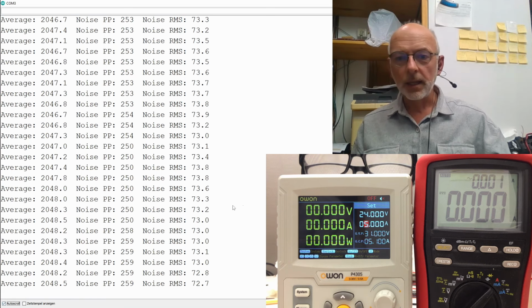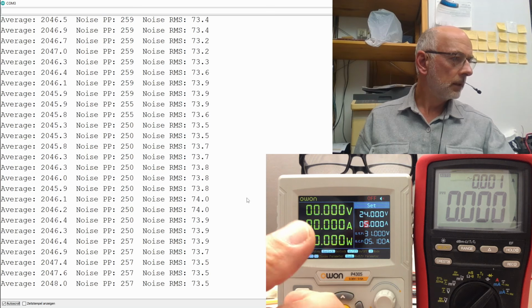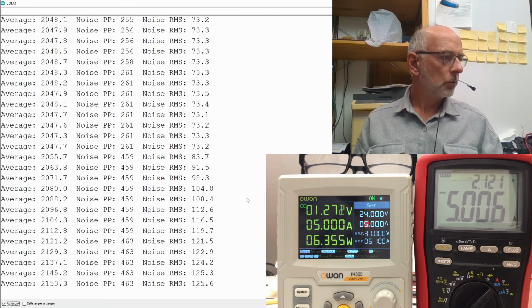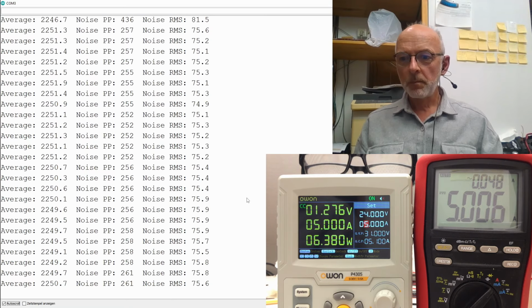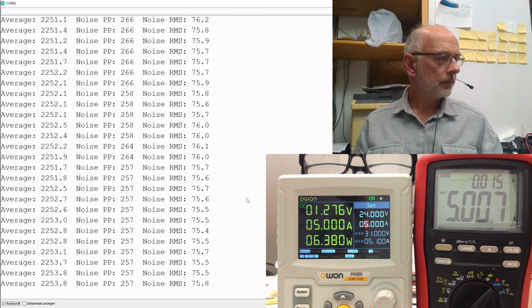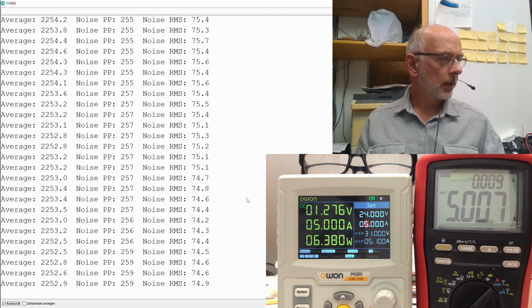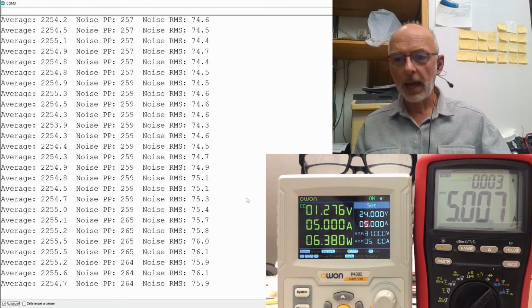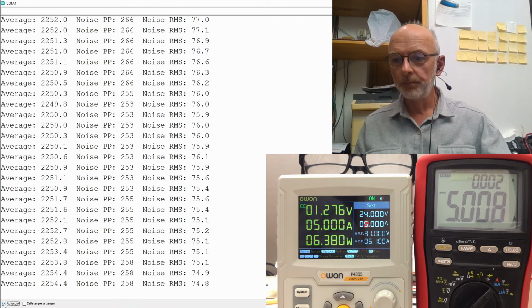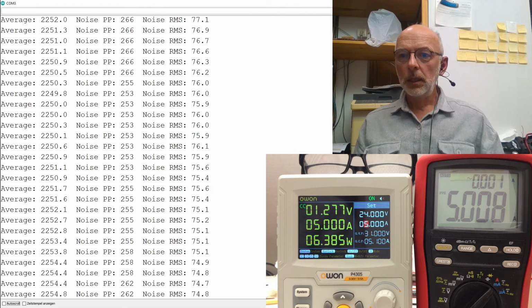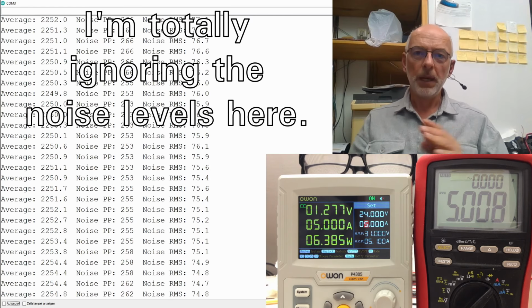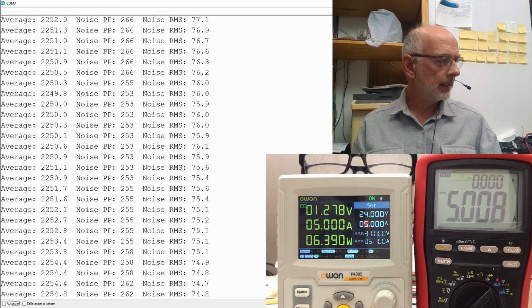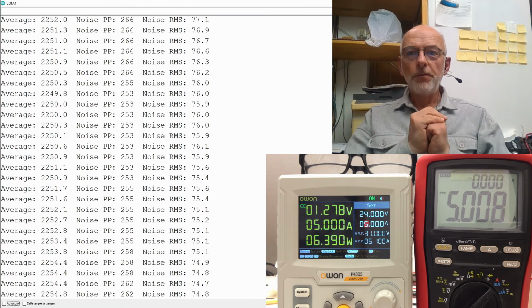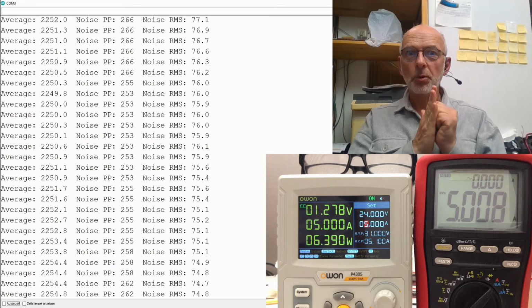So let's get auto scrolling again and go to our second calibration point, which would be 5 amps. And of course, we see a change here. I saw just a digit flip here. Give it another second until it's really stable. Yeah, 5.007 amps. Yeah, let's believe that for now. Stop again here. Yeah. Looks good to me. As I said, I will do offline min-max center value analysis of that data too. Let's move on to the voltage calibration, shall we?